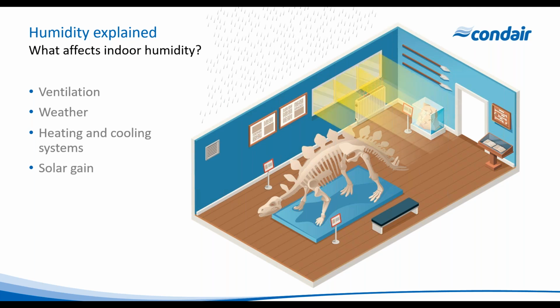Solar gain. Alongside factoring in mechanical heating, solar gain will also impact the indoor environment, very much depending on the U value of the glass. That is going to have a sensible heating effect inside the room. Again, that will depend on building orientation, the type of glass, and the surface area of the glass panels. People, as well as potentially contributing moisture via wet clothing, naturally add moisture to a building through breathing. Now, typically, this can be calculated at 35 grams per hour for a person sitting, whilst this will rise to 110 grams per person per hour for somebody with a medium intensity of activity, and 185 for activities like exercising. So typically in a heritage application, we would expect to add 35 grams per person per hour.